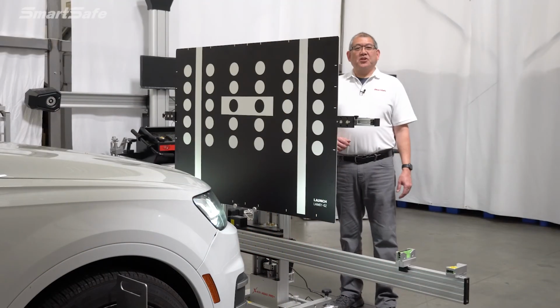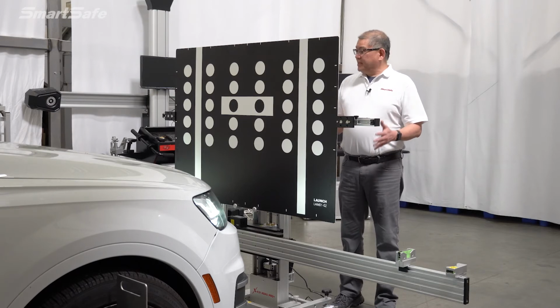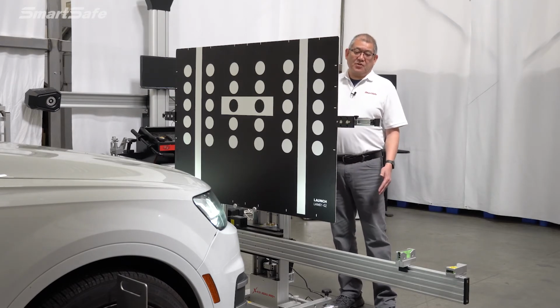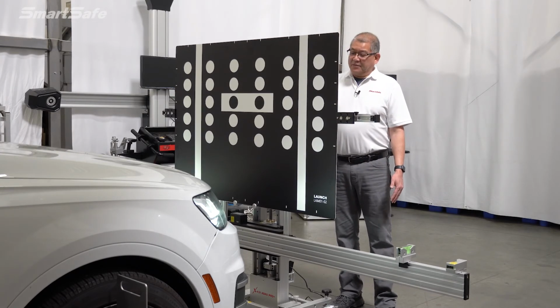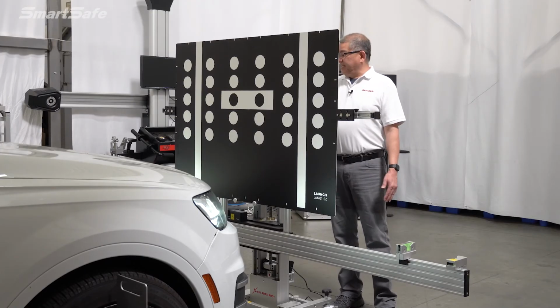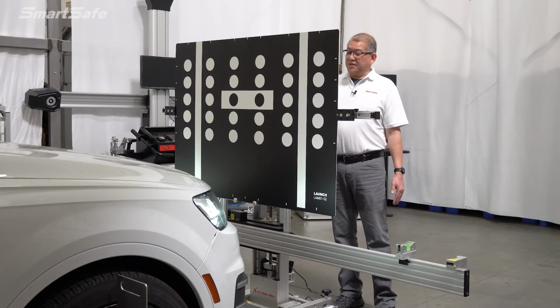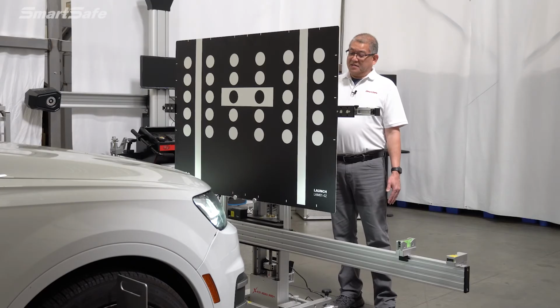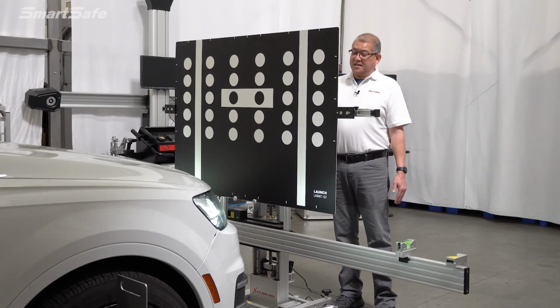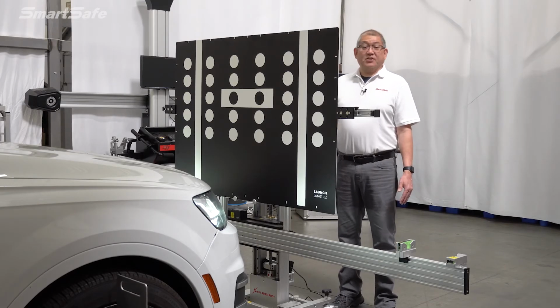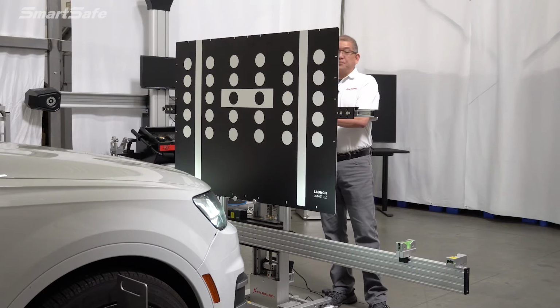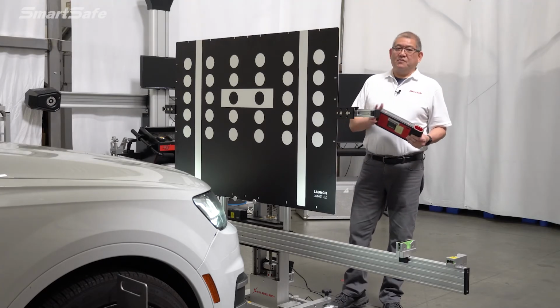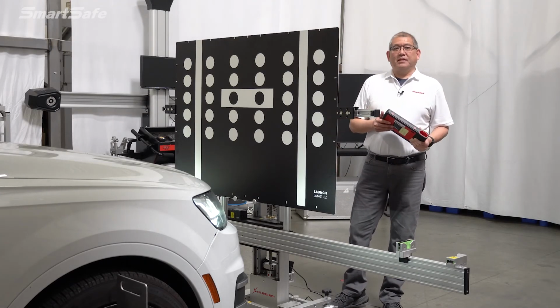Our last step is to go ahead and adjust the height of the frame. So this has a power lift, so we'll go ahead and engage that. And we need to be at a height of 1330. So we're almost there. Actually a little too high. And we'll crank it down with the manual adjustment knob in the back. And we're at 1330. So at this point we're ready to calibrate, so I'm going to go ahead and move myself away from the camera, out of the view of the camera, and we'll go to our next step.